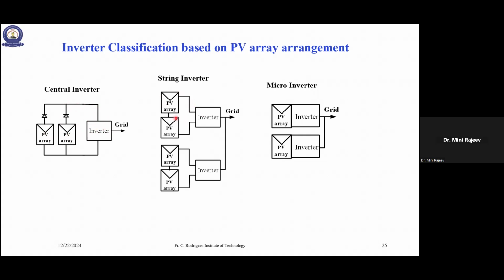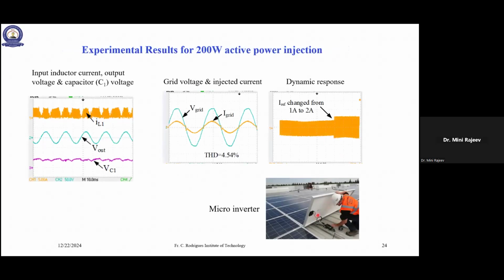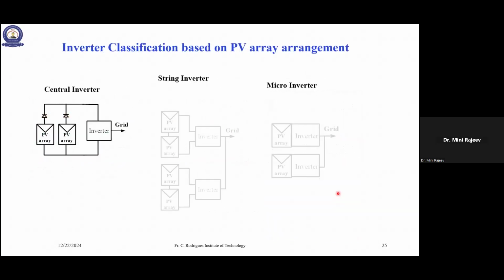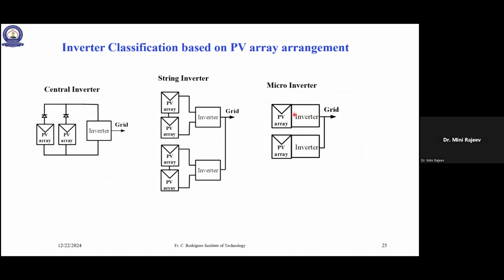In a string inverter, efficiency-wise it will be better, but still a string of PV arrays is connected to one inverter, another string to another inverter, like that. Here, each PV panel is fitted with its own inverter. The drawback is that you cannot have it for very high power levels because the size and weight will increase. This is the photo I have shown: a micro inverter fitted below the PV panel. The advantage is that the MPPT efficiency will be higher because each panel has an inverter fitted to it, where we do MPPT. So the conversion efficiency will also be higher. For residential applications, micro inverters are preferable.